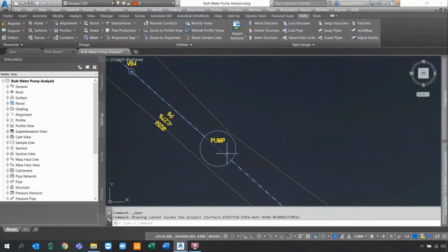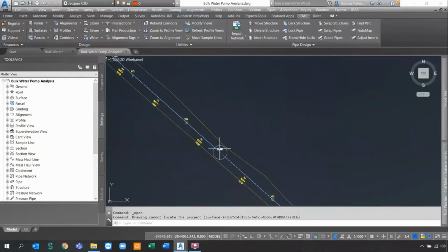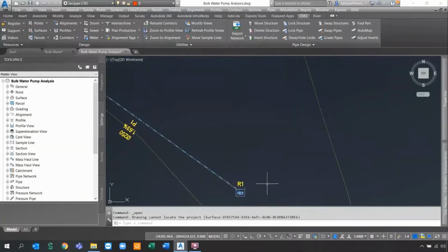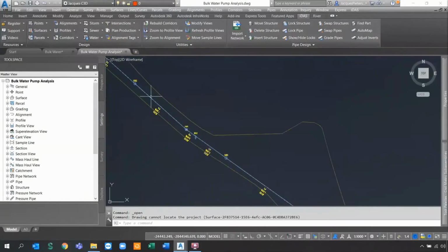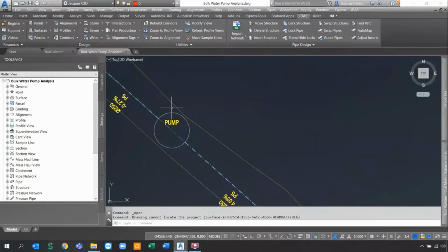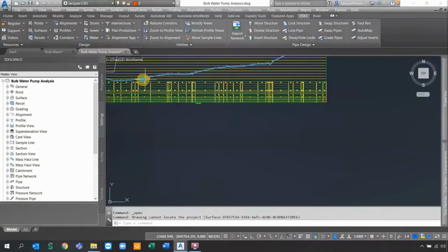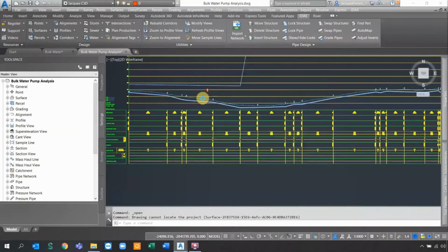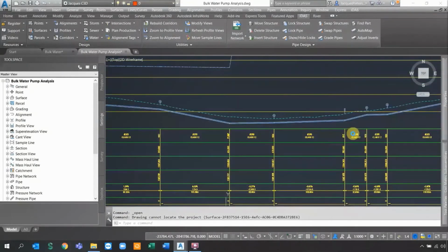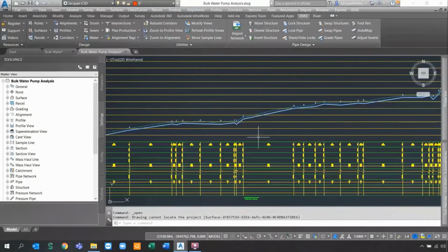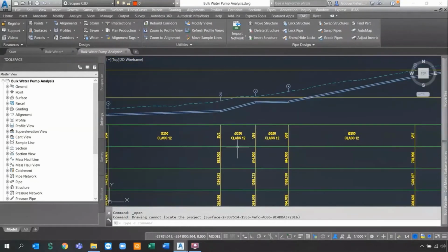So what I want to do is actually add a pump to the system, but first I need to know what my system curve is, because currently I don't know if this water is actually going to reach the tank at the end of the day. So I need to swap out the structure to a junction, or any junction type it can actually be used as. Then I need to set up some settings inside of my Devotech iDas that will give me the system curve.